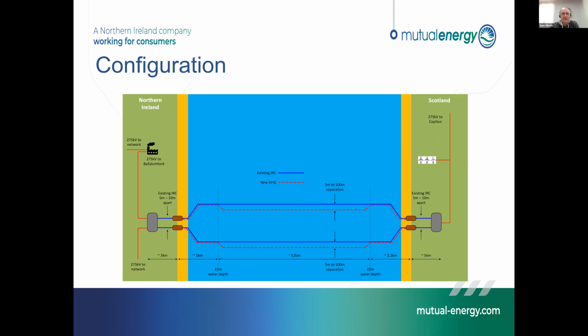And then you can see the connections on either side to the 275 kV networks. Here in Northern Ireland, those are really strong connections. We're adjacent to 2 of the local power stations and tied in by 2 circuits into the 275 network. On the Scottish side, it's a much weaker connection. We have a single 275 connection. We're about 60 kilometers away from the nearest generation, other than wind, and so the stability on the Scottish side is much less. The fault level there is now starting to get to low levels below which an LCC converter struggles to operate efficiently. That's one of the things that we've looked at in the control system upgrade.